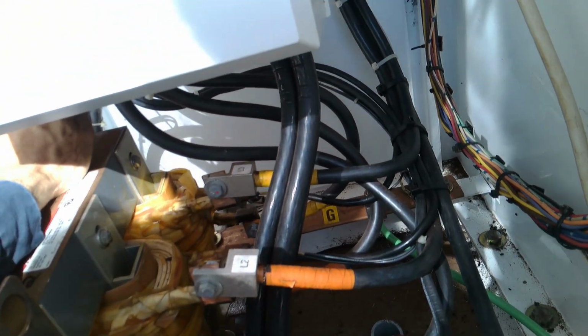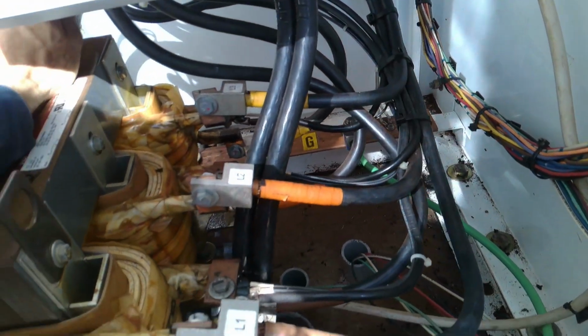Right back here. I don't know if you can see that. That big bolt right there. That's a ground wire that runs up right into the, what is that, line side of the drive. And he's landed on there. So the drive is grounded and bonded. So it's grounded to earth and it's bonded to the casing of the metal of the motor. Just wanted to make sure there wasn't any weird grounding thing going on.